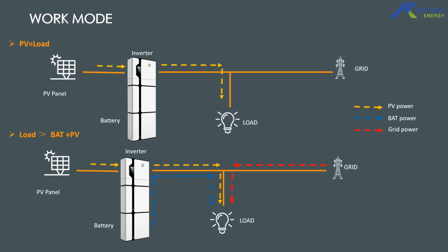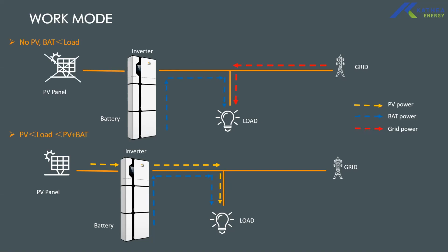When you have grid and your battery discharges to the set reserve SOC, then the system would use PV and grid to supply your loads, and the battery will be kept only to be used when there is load shedding. So when you don't have PV and the battery is less than the load, whatever the battery can supply, the system would use, and then the excess it takes from the grid. That is usually in night scenarios.